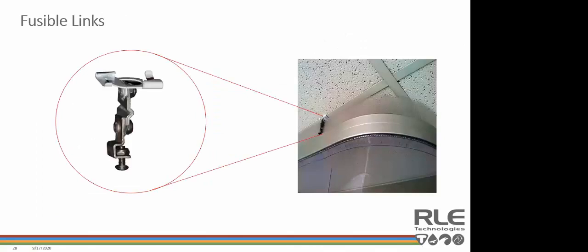Fusible links are also often used in our containment solutions, typically with our soft containment options. A fusible link is made up of two pieces of metal that are linked together with a material that has a very specific melting point. In our projects, depending on customer needs, that activation point is either 135 or 165 degrees. When the temperature reaches the activation point, basically the lower part of that fusible link will drop away from the top part. This allows the curtains to fall away from the ceiling, providing access by fire suppression systems to the previously contained area.